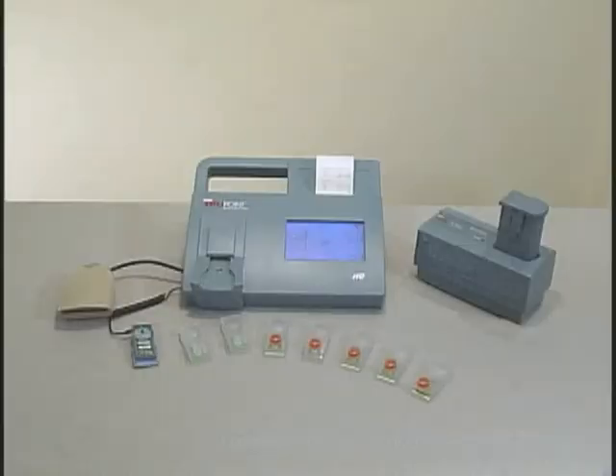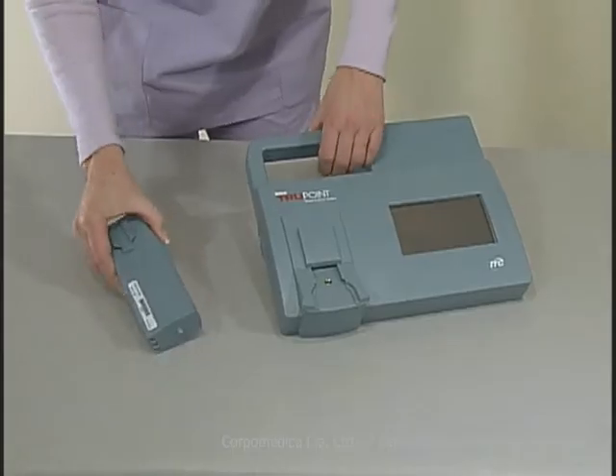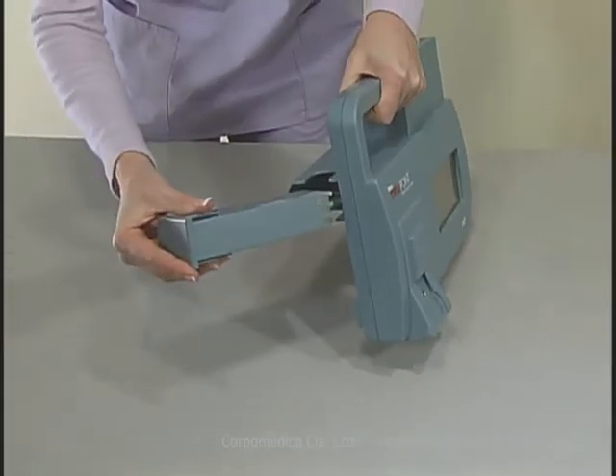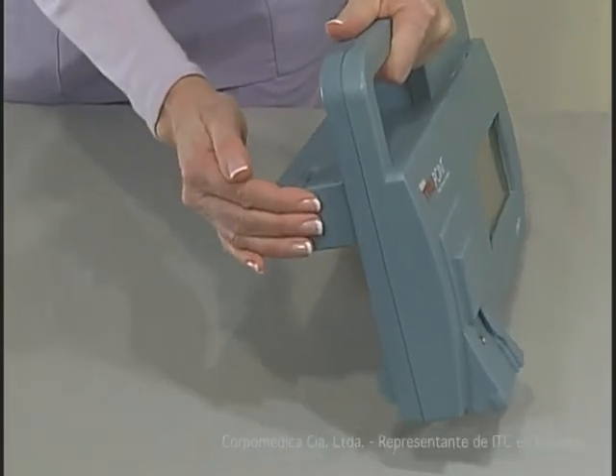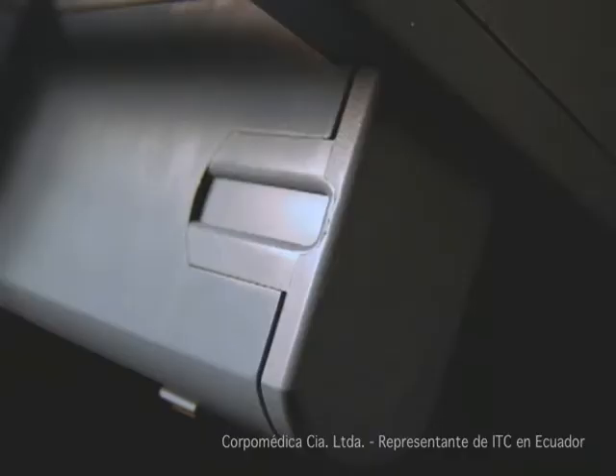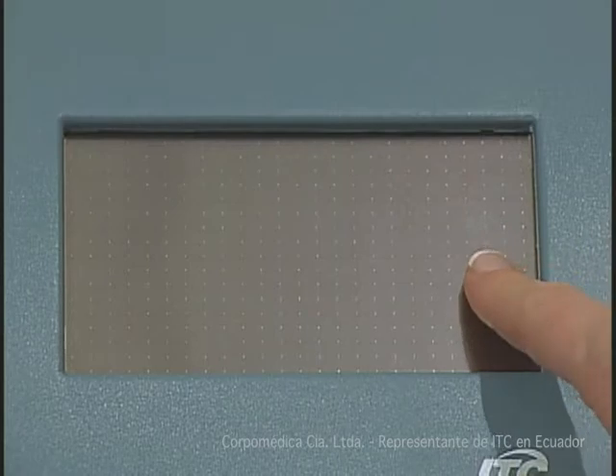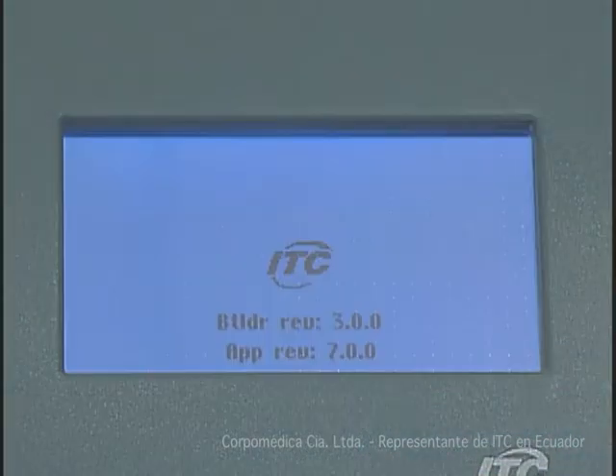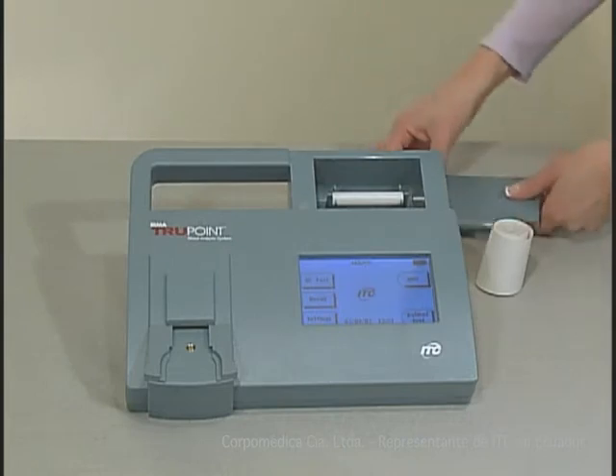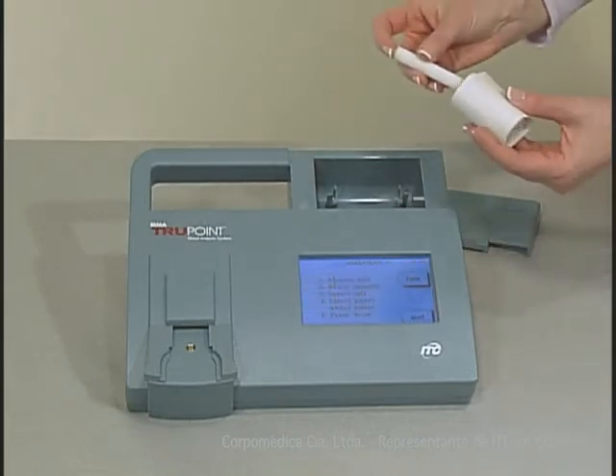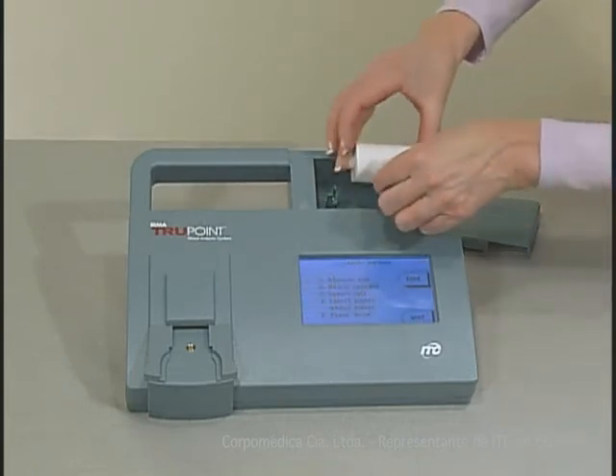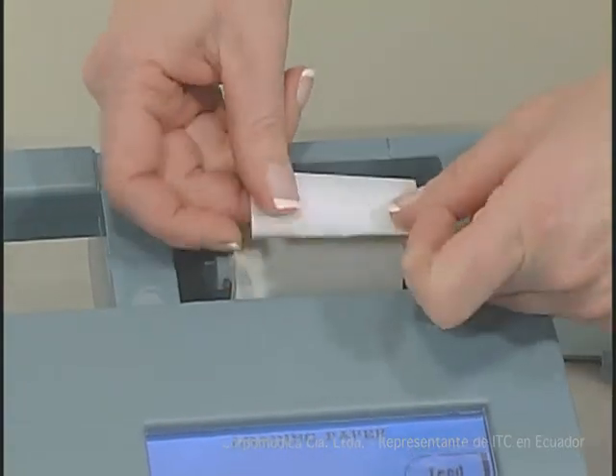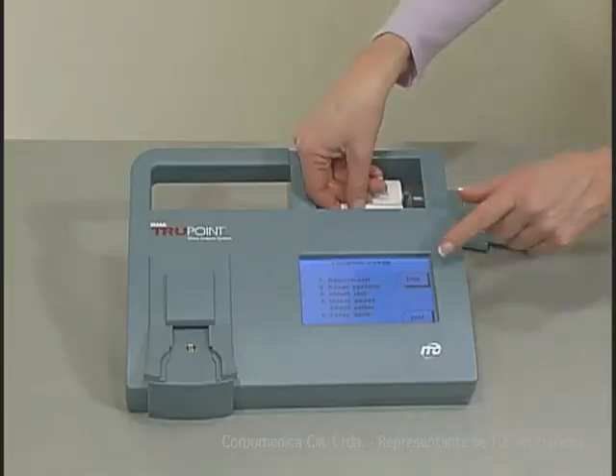The analyzer can be operated with either an AC power adapter or the battery. Both the AC adapter and the battery can be easily inserted into and removed from the side of the IRMA TruPoint unit. To remove, depress the clips located on the side of the battery or the AC adapter. To turn on the analyzer, touch the right-hand side of the screen. Load the printer paper by removing the printer door and following the instructions displayed on the screen. Only use paper provided by ITC. If the printer fails to print, check that the paper has been placed under the spindle.